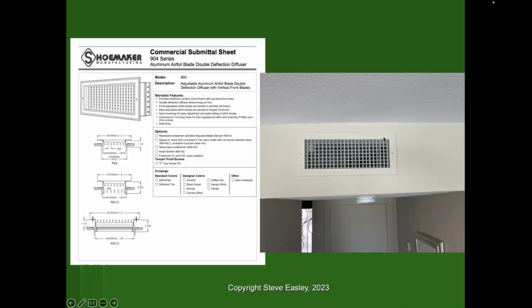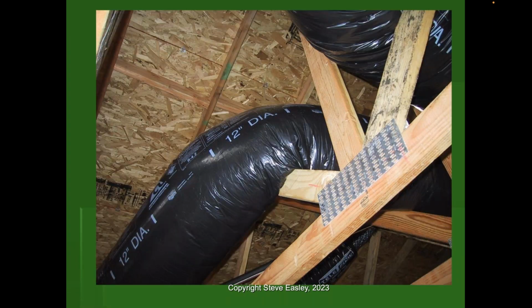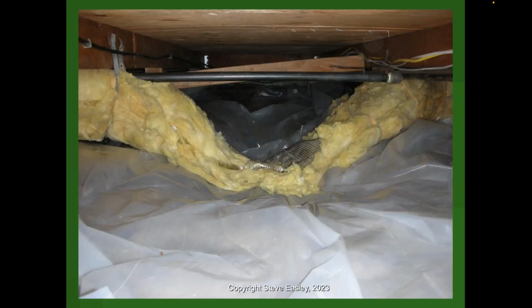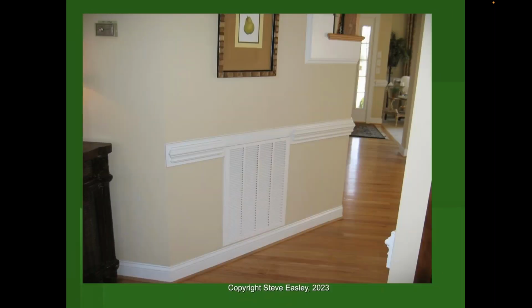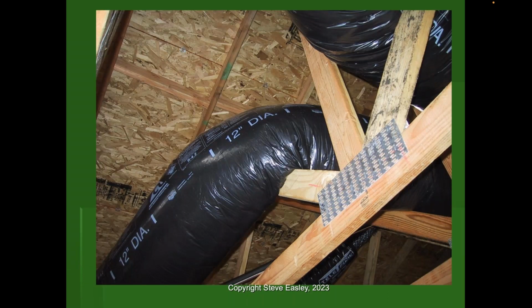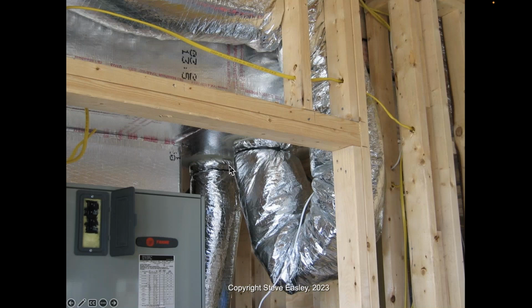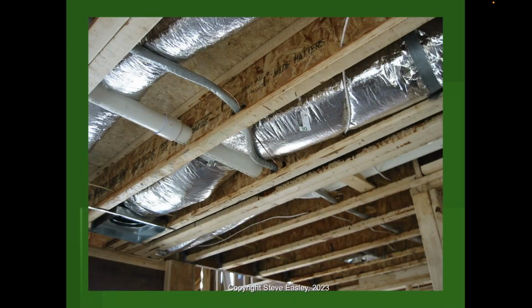Here are some supply registers. This is what I have in my own home. Even in my older house, I replace these. So these give you airflow that broadcasts the air much deeper into the room, with much less restriction than you see with these types of, let me go back here, with these types of grills. Okay. And again, look out for problems like this. This is just the kiss of death. When you see these types of restrictions, it has a huge impact on any system's performance, not just heat pumps. But these are the kinds of things that we need to pay close attention to.